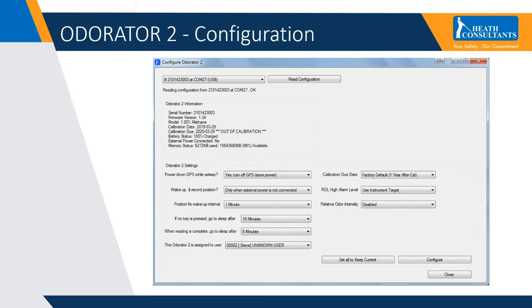It will alert the operator, who has to acknowledge with the keypad, but the instrument will still be functional even though it would report that it's out of calibration.